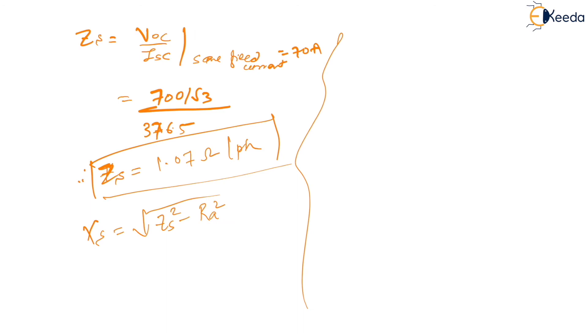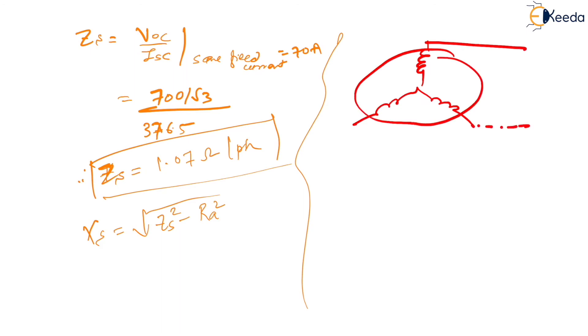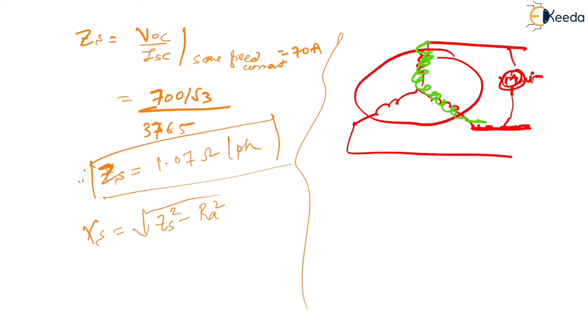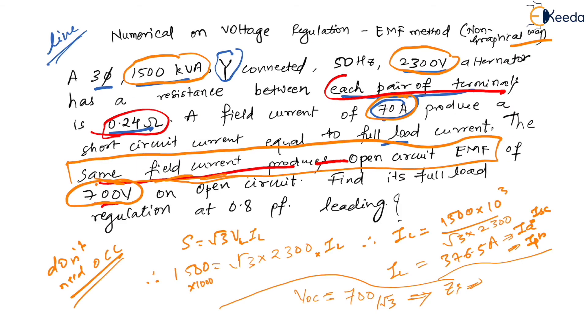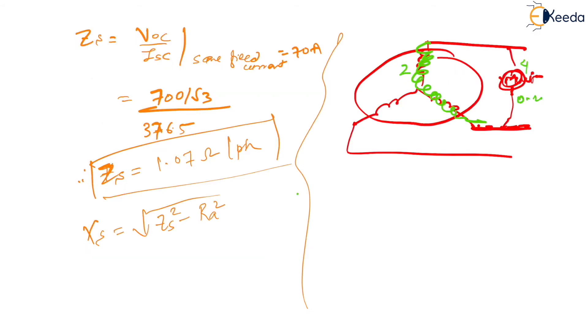'Each pair of terminals' means you measure resistance across two external terminals of the machine. That path goes through two phase windings in series, so the measured value equals two times the per-phase resistance. Therefore, RA per phase = 0.24 / 2 = 0.12 ohms.